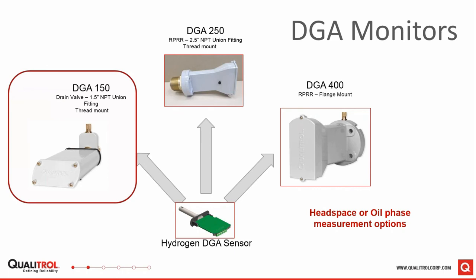Incidentally, the DGA250 and 400 are for pad-mounted transformers. The same sensor, the same performance, but they both have an integrated rapid pressurized relay. And the difference between those two products is just the connection point. One of them is a 2.5-inch NPT union fitting, and the other is a flange mount.